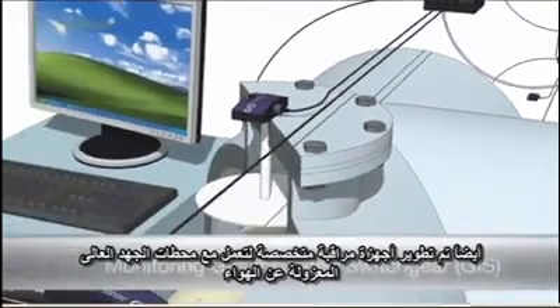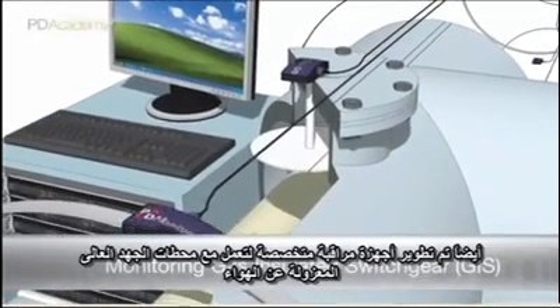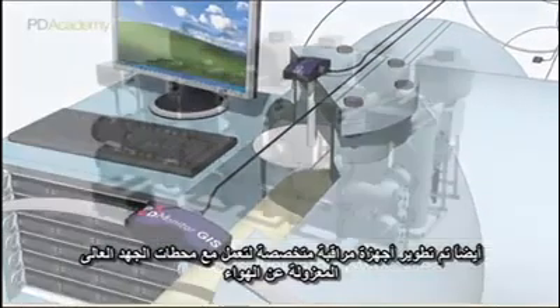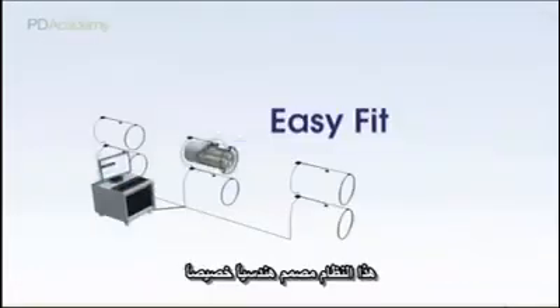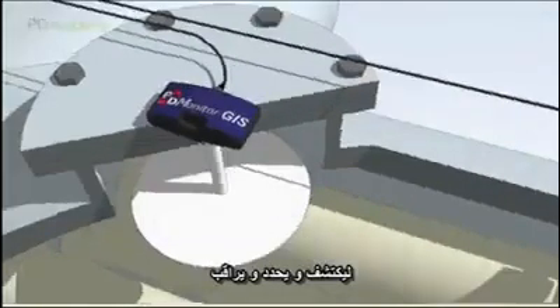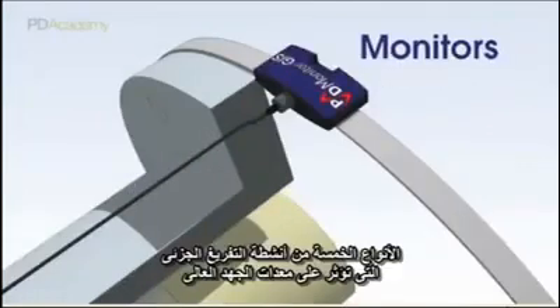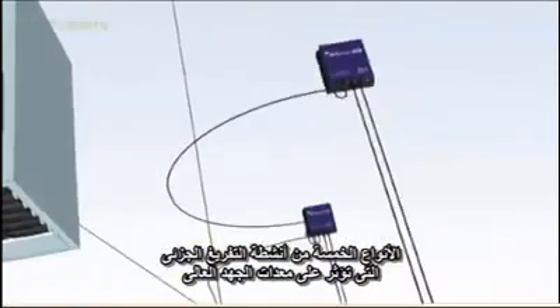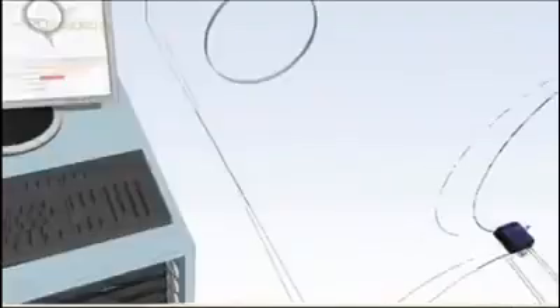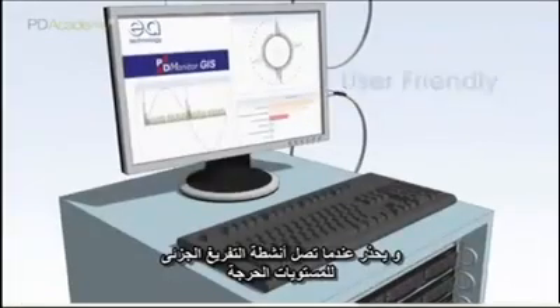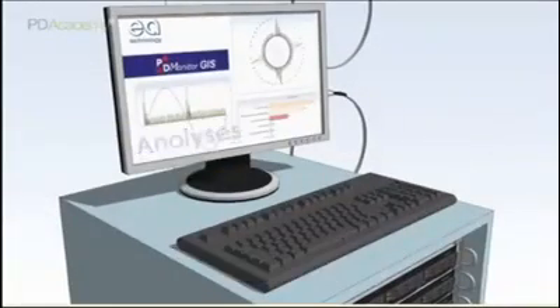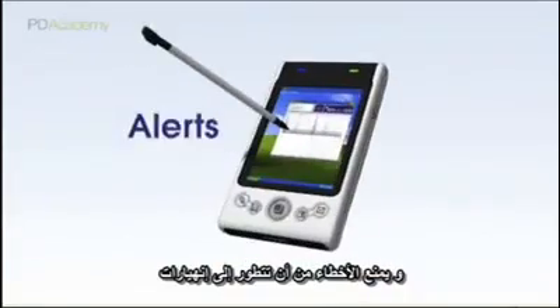Specialist monitoring and alarm systems have also been developed for extra high voltage gas insulated switchgear. These are specifically engineered to detect, locate, identify and monitor the five different types of PD activity that affect GIS assets. To warn when PD activity reaches critical levels and prevent faults developing into failures.